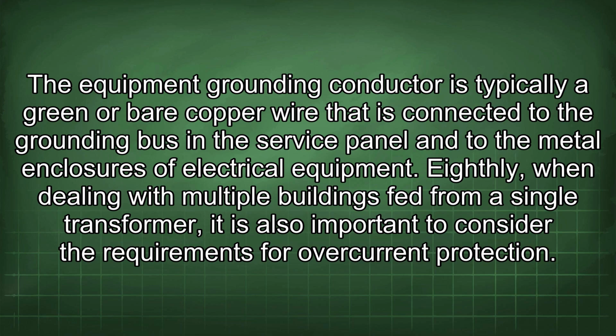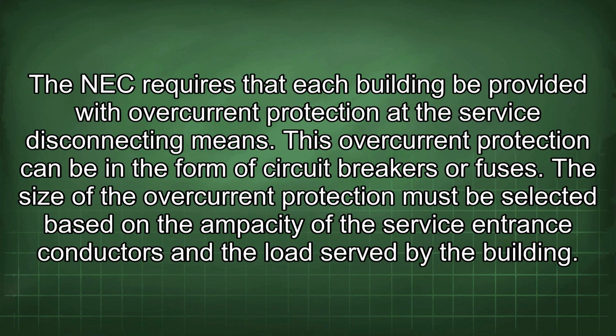Eighthly, when dealing with multiple buildings fed from a single transformer, it is also important to consider the requirements for overcurrent protection. The NEC requires that each building be provided with overcurrent protection at the service disconnecting means. This overcurrent protection can be in the form of circuit breakers or fuses. The size of the overcurrent protection must be selected based on the ampacity of the service entrance conductors and the load served by the building.